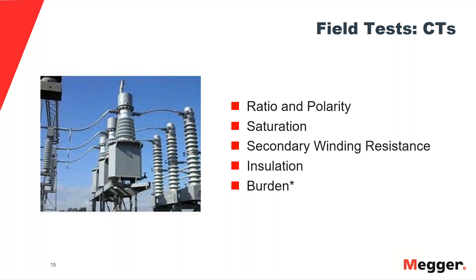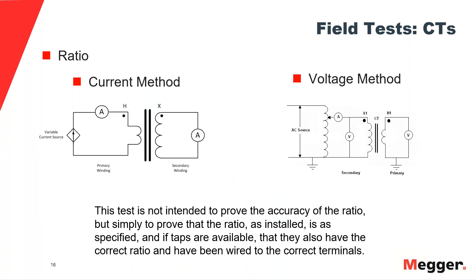All of these tests are described in the standards, both IEEE and IEC. Let's start with the ratio test. For this measurement, we have two methods available. The first, sometimes called primary injection or the current method: we connect an AC current source to the primary side of the current transformer, inject a current, and measure the resulting induced current in the secondary side. This pretty much reproduces the exact same condition of the CT when it's in service.